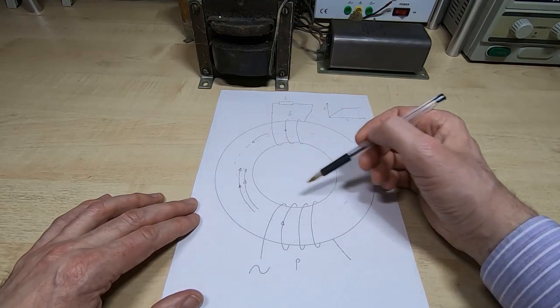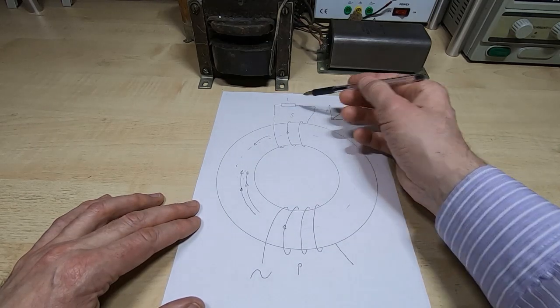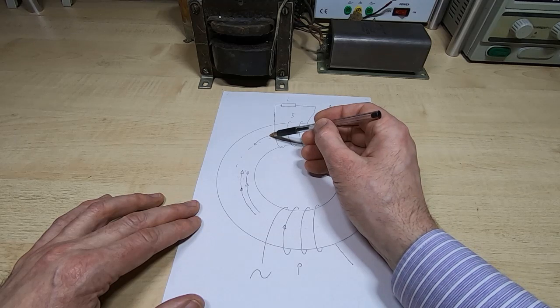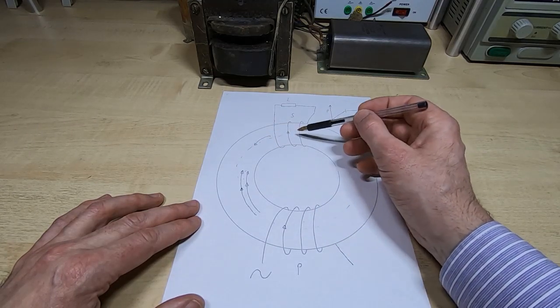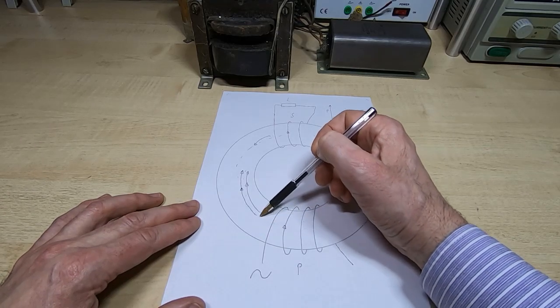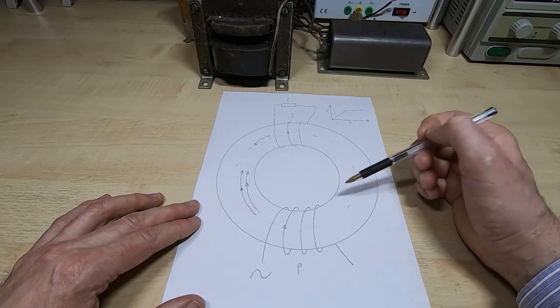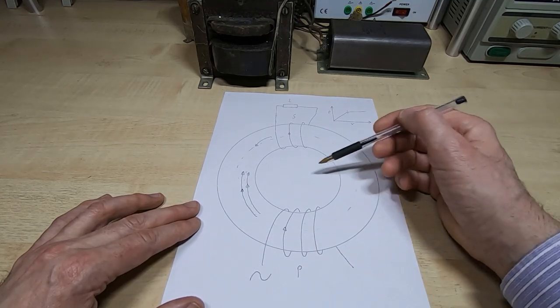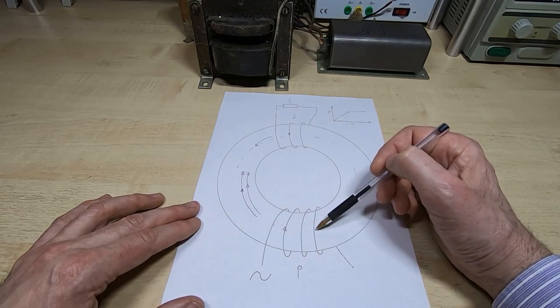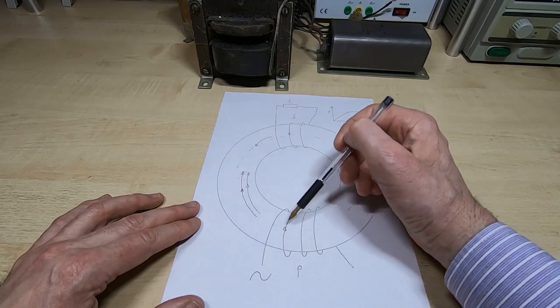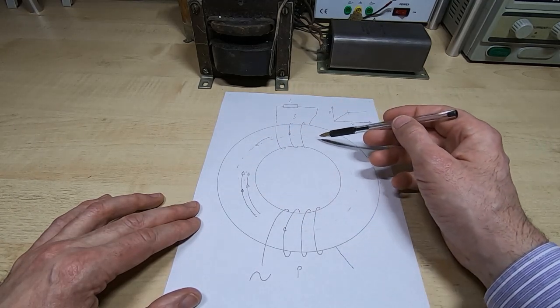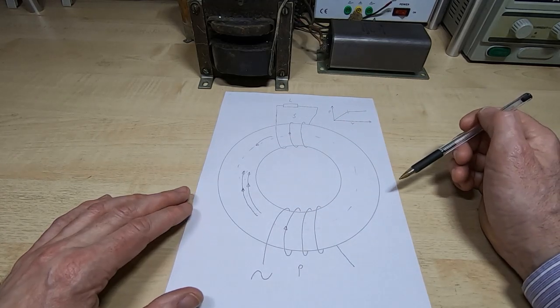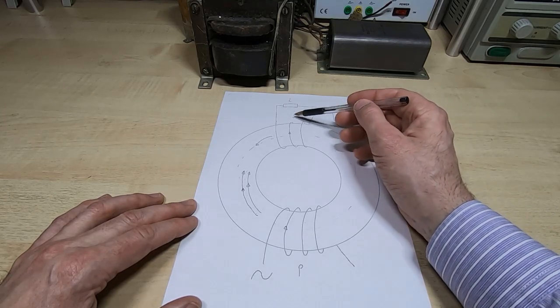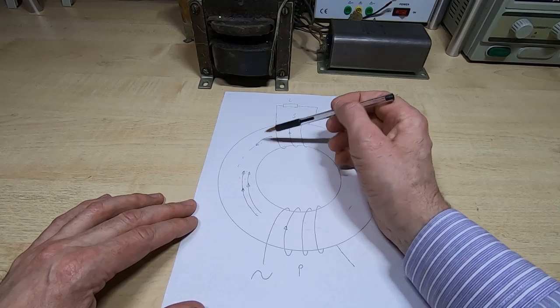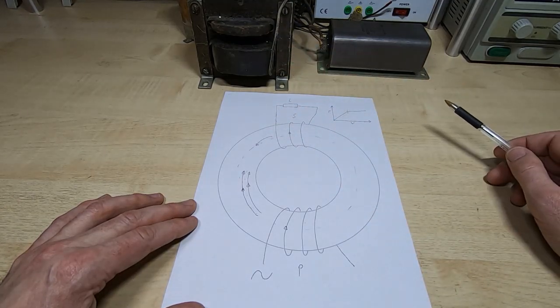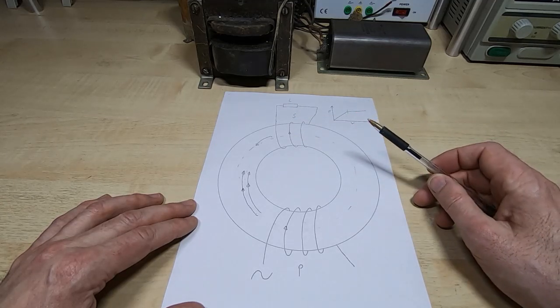And that's how the energy transfer between the two windings takes place: as the load on the secondary increases, the reversal of the flux that's being generated by the secondary winding causes the current in the primary to increase to keep the flux generated by the primary up to the level that the transformer wants to try and generate. That's why the current drawn by a transformer is low when there's no load, and why the transformer is able to respond and transfer more energy through the core as you apply a load. That principle of the secondary generating a flux in the core is very important to the way that a ferroresonant transformer works, so just bear this in mind as we start to look at the ferroresonant transformer.